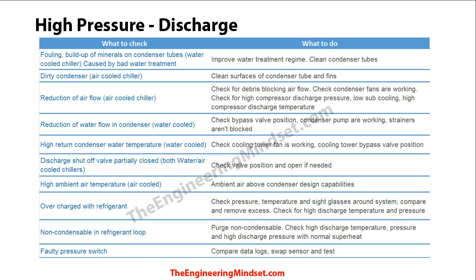At the top we have fouling, which is a build-up of minerals on the condenser tubes. This is very common in water-cooled chillers and is always caused by bad water treatment regimes. With open cooling towers, minerals and dirt absorbed from the air get into the condenser water, flow around the system, and clog the pipes and heat exchanger tubes, effectively insulating the condenser so heat can't be transferred.